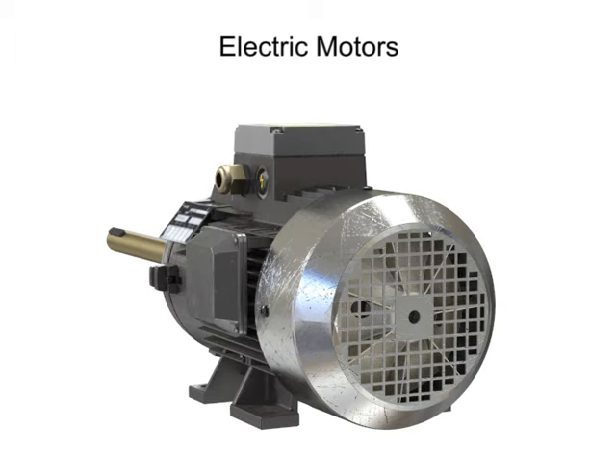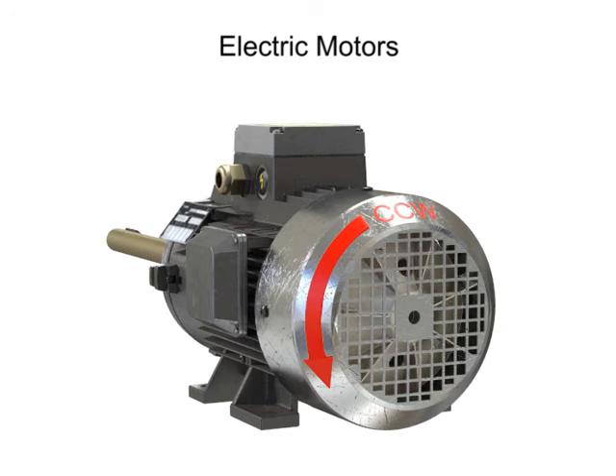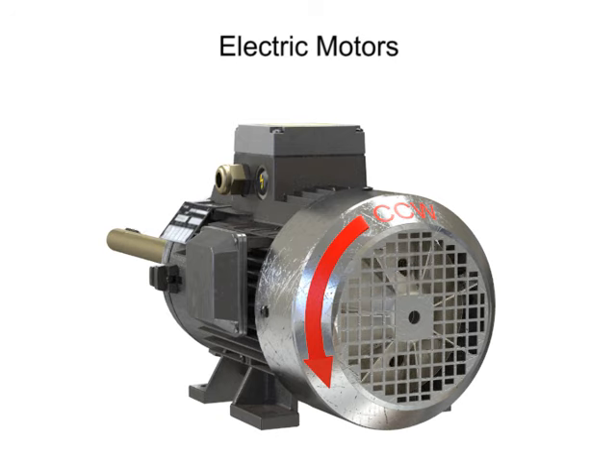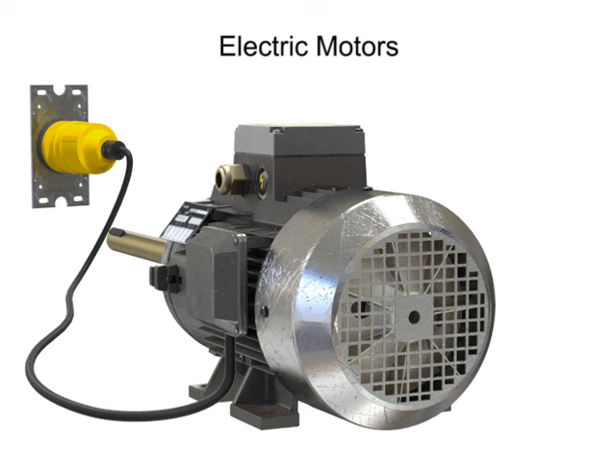There are many types of electric motors used for a variety of purposes in commercial industry. One critical task that must be performed prior to installing a motor is determining the motor's correct rotational direction. If a motor is required to rotate in a specific direction, it will have a direction arrow prominently displayed on the frame. But with few exceptions, most three-phase motors are made with symmetrical parts so the motor can rotate in either direction. Since these multi-directional motors are equally efficient in either direction, there's no standard direction of rotation.